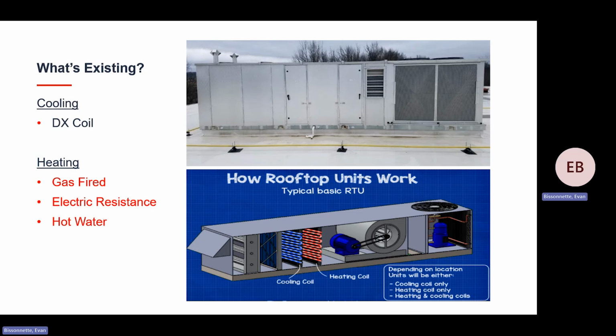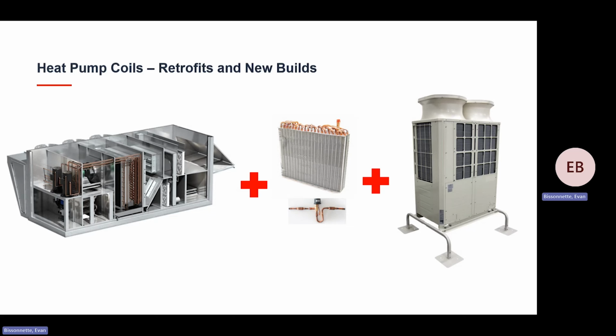So what we're proposing is to retrofit these types of rooftop units with a heat pump coil. So what does that mean? You have your existing rooftop unit, say it's 5 to 10 years old, the supply fan still works great. We can remove the existing heating coil in that unit, select a new heat pump coil to match the existing CFM or load in that space, and pair it with one of our heat pumps using a linear expansion valve kit or LEV kit. So we'd have a new coil connected to one of our condensing units that's now getting heating and cooling with the efficiencies of a VRF heat pump system, and we're removing all of your gas from your building.